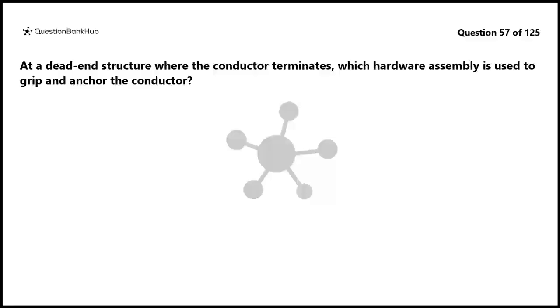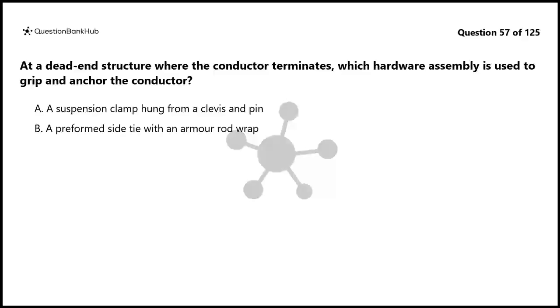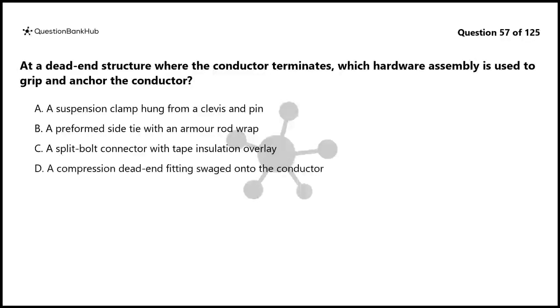Question 57. At a dead-end structure where the conductor terminates, which hardware assembly is used to grip and anchor the conductor? A. A suspension clamp hung from a clevis and pin. B. A preformed side tie with an armor rod wrap. C. A split bolt connector with tape insulation overlay. D. A compression dead-end fitting swaged onto the conductor.